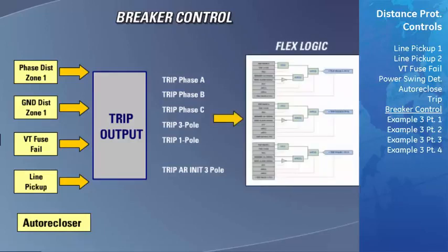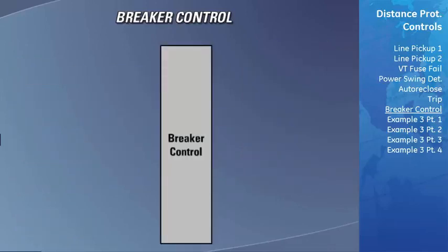The next step in programming your D60 is to take all of these control outputs and create a scheme using flex logic. This scheme will take all of these outputs along with all of the contact inputs which show the status of your breaker and create your tripping logic. However, just like the trip output scheme we discussed earlier, the D60 has a pre-configured scheme to handle all of this logic for you. It is called the breaker control element.